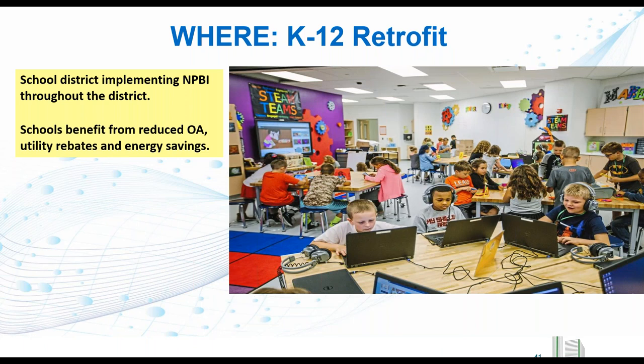We'll talk for a minute about K-12 retrofit. Darlene has been working with the school district to have needlepoint bipolar ionization installed throughout the district. And for each school, it's analyzed how much outdoor air reduction is available, if it's a renovation and equipment can be downsized, that's great. That's a savings in equipment. But that's not always the case. Sometimes we're just going and retrofitting. So then it's just reducing outside air dampers, reducing the amount of air that's brought in, and we get energy savings by not having to heat and cool that air. The local utilities offer rebates on that, and it's been working beautifully throughout the school system.